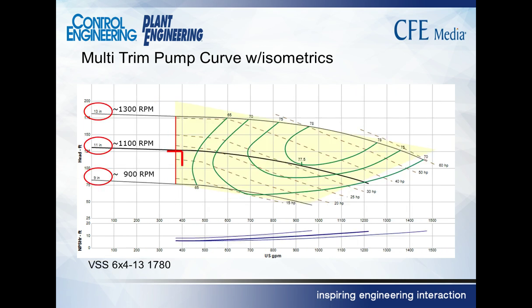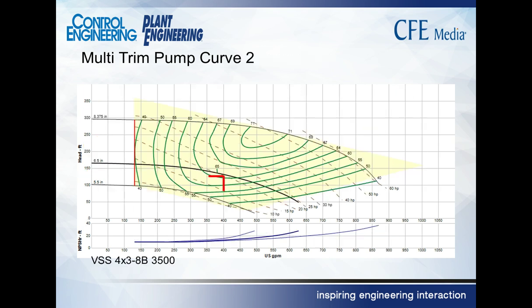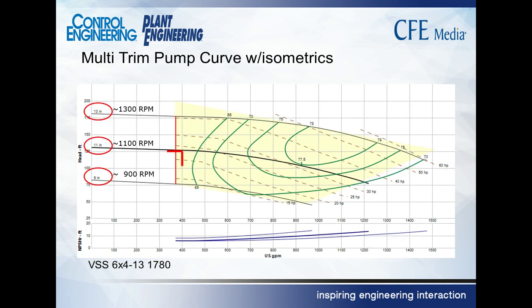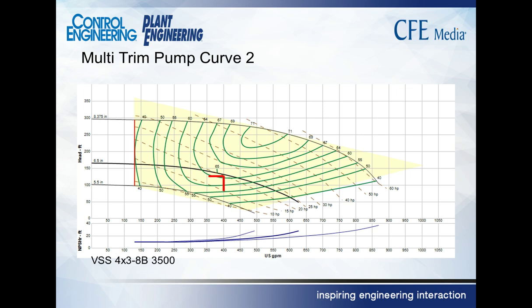And I said, well, what's the efficiency on those pumps? And he said, well, the best efficiency point on the bigger pump is 77.5%. And the best efficiency point on the smaller pump is 65%, 66%. I said, well, I want that nice big heavy pump with that better efficiency. Well, wait a minute. Not at our operating point. At our operating point, the efficiency is 50%, and the pump's going to run warm and the pump's going to run rough. Much better off with the smaller pump.